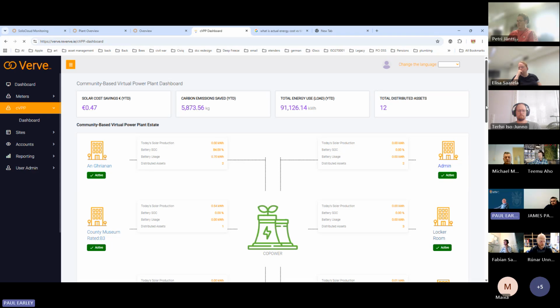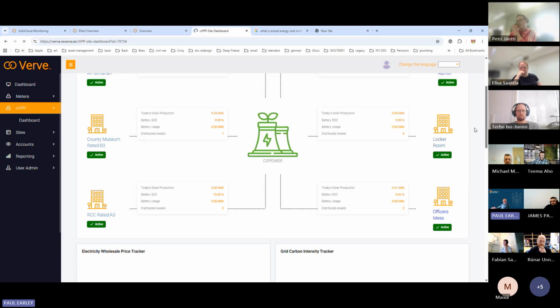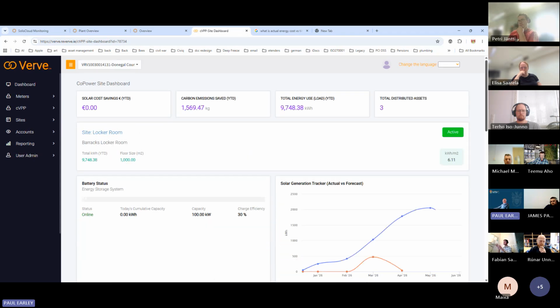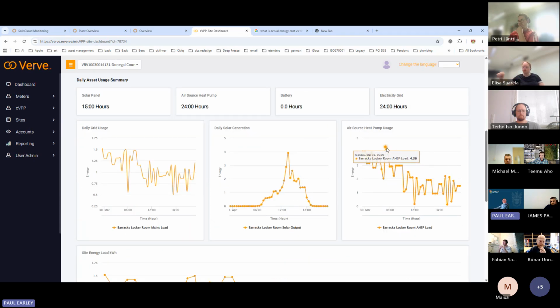One of the main outputs we discovered is that in each of these buildings they have air source heat pumps, and these were consuming about 80% of all the electricity used in the buildings. This hadn't been spotted before because there's no smart metering on these sites. So one of the first things we did was install sensors or meters to measure the total energy consumption from the grid coming into the building, and a separate meter to measure the electricity consumption of the air source heat pumps.